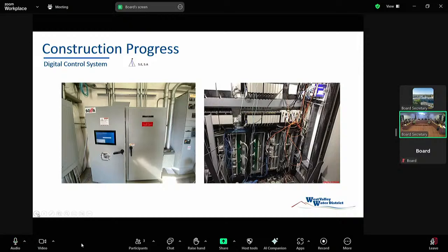What you see here is one PLC and a bunch of input and output cards. If that one PLC fails, that's a single point of failure that could theoretically take down the plant until operators can respond. So the way a lot of districts mitigate that is they have a second redundant PLC, which is what you see right below there.